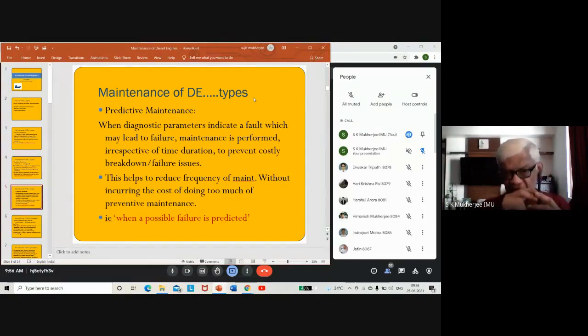So you have a sensor on that which can transmit that frequency continuously to a receptor. And that receptor receives the frequency of vibration of that component continuously, and records it into your computer, in your database. So in your database, you have already got 327 recorded for number 7 unit connecting rod. And the signal coming from the connecting rod through your transmitter receiver devices is 327. So everything is fine. It is vibrating at its normal frequency.